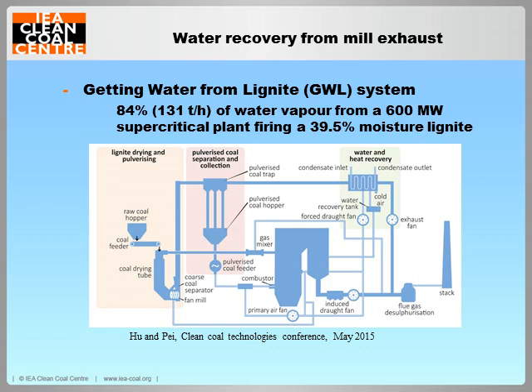One technology being developed in China to recover moisture from coal is called the getting water from lignite system. High temperature flue gas extracted from the upper part of the boiler and low temperature flue gas from the rear of the boiler are mixed and used to pre-dry the raw lignite in a drying tube. Evaporated moisture and coal then enter a fan mill where further drying of the coal occurs. The vapour and pulverised coal are then separated and the vapour is condensed in an ultra-low temperature heat exchanger. Field tests of the system have been carried out on a 100 megawatt unit.